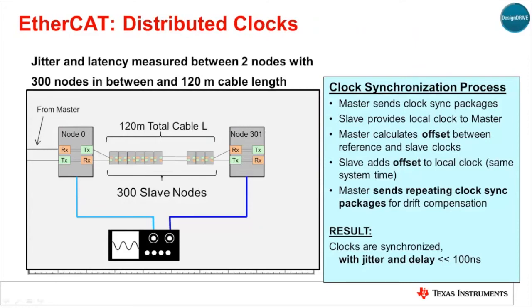One of the most powerful features of EtherCAT for real-time control is the distributed clocks unit. IO activities can be triggered from master cycle timing or local clocks in each slave. These local clocks can be synchronized to a reference clock in the system, which is either the master's clock or the first slave. Since the EtherCAT master may typically have higher jitter and delay compared to the slave nodes, the first slave is more commonly used as the reference. The master manages the measurement of delay and drift through a clock synchronization process, using repeating clock sync packages to determine the required offset for each slave, enabling it to maintain a clock with jitter and delay much less than 100 ns.